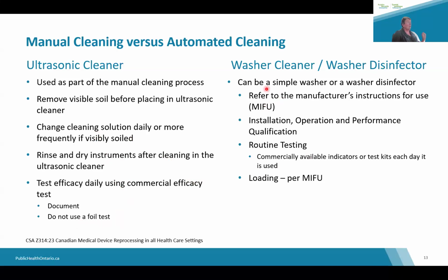And then we move to the automated. You can use a washer cleaner or washer disinfector, but you need to refer to the manufacturer's instructions. You need these for the installation, operation, and performance qualifications of the machine, and then for the routine testing. To make sure that the machine is working optimally, every day you need to test it with a commercially available indicator. And when it comes to the loading of the machine, you need to follow the MIFU, because every brand of machine may be slightly different. So the manufacturer's instructions for use are very important.